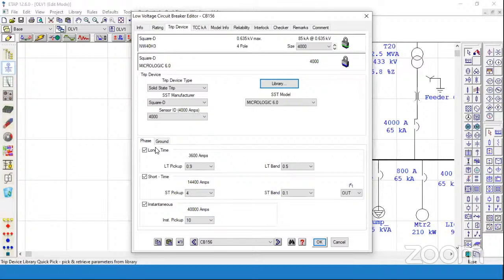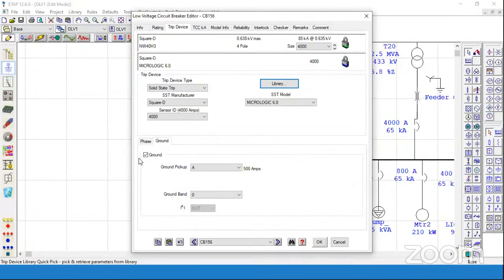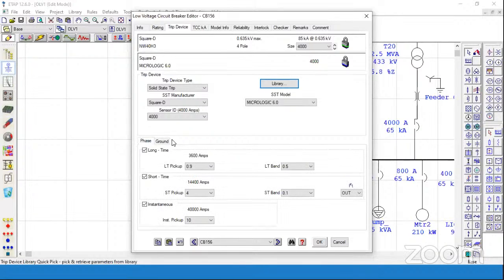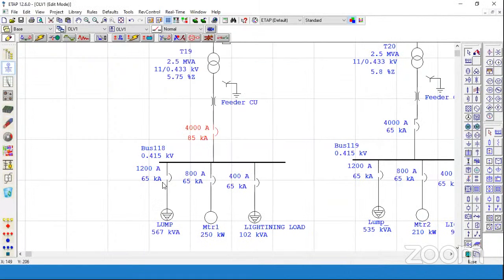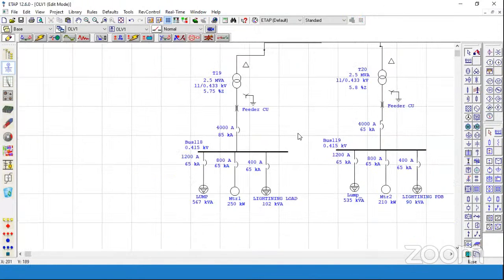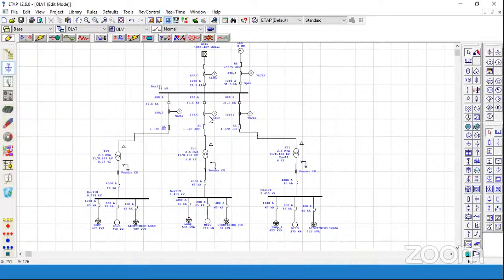The trip device is LSIG, meaning long time, short time, and instantaneous protections, which we need to give, and then the ground fault protection. For ground fault protection there are certain setting parameters which we need to give as input in this section. Then certainly the outgoing loads, that is lump load, the motor feeder, and any lighting load connected to this network with different ratings and parameters. Likewise, a typical network has been modeled over here for easy understanding of the relay of this system.